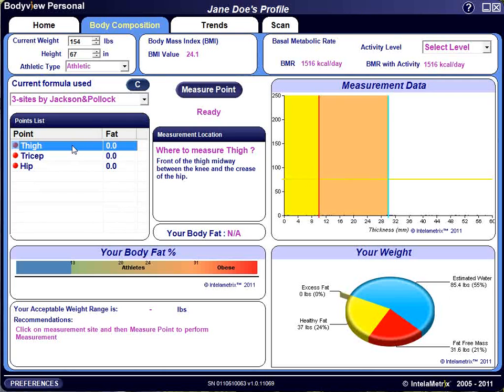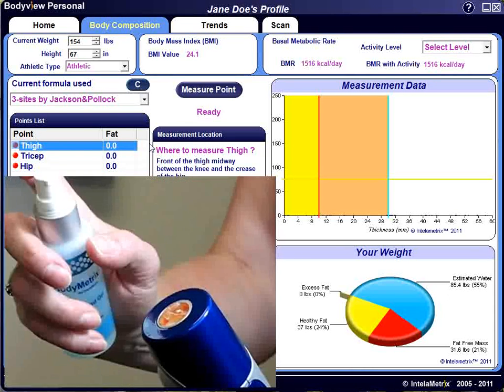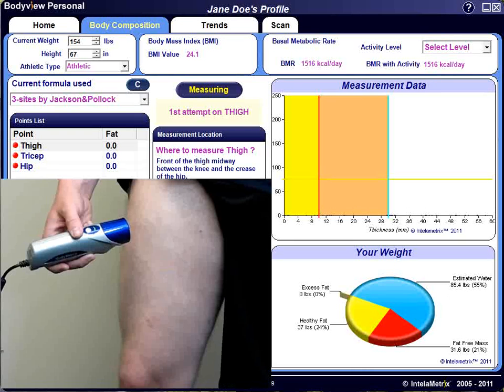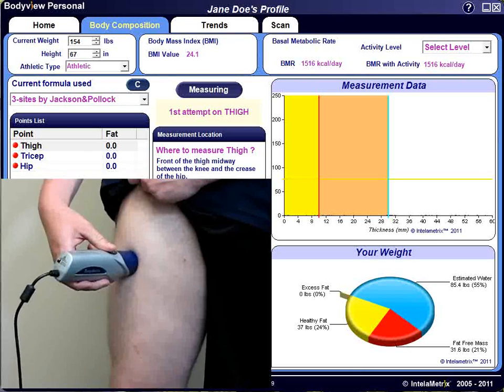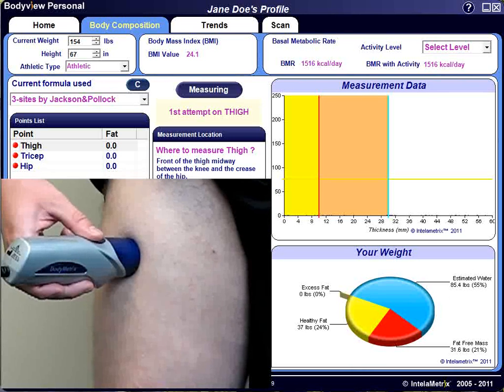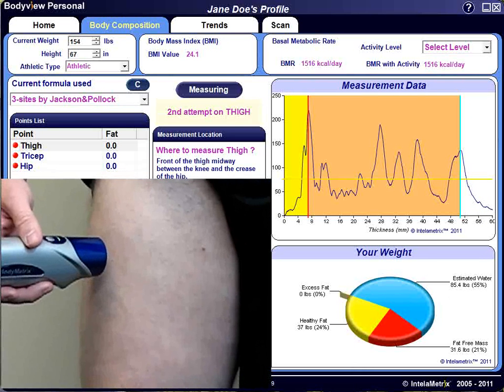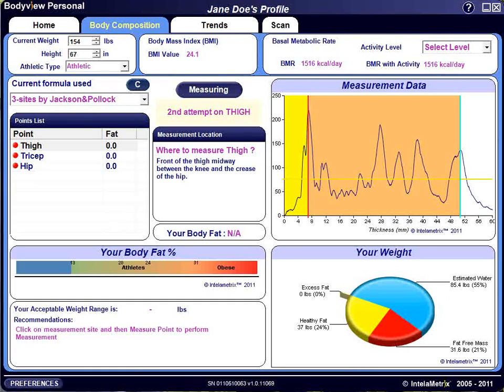Highlight the first measurement point on the point list. A description of how to measure the point will appear in the measurement location box. Apply a small amount of ultrasound gel to the tip of the ultrasound wand — about the size of a pencil eraser. Click on the Measure Point button. Place the wand on the measurement site. The device must touch skin. Spread the gel by moving the device to provide a thin layer over a 2 to 3 inch area. While maintaining contact with the skin, press and hold the device button while moving the device slightly up and down or side to side — about a quarter of an inch in either direction. Hold the button for 3 to 4 seconds and release. This technique is called averaging. Since fat is not an even layer, averaging provides a representative average of the fat at each location.